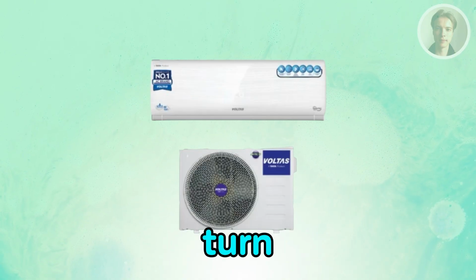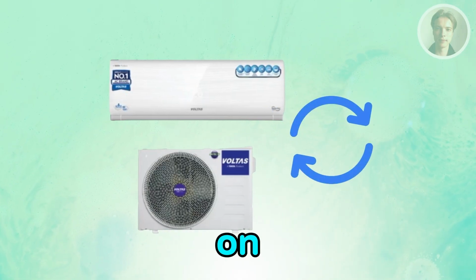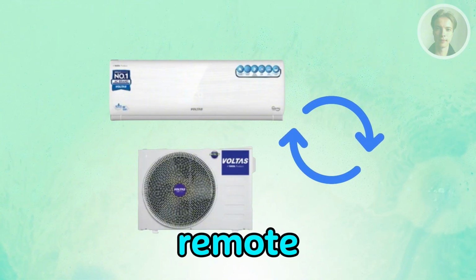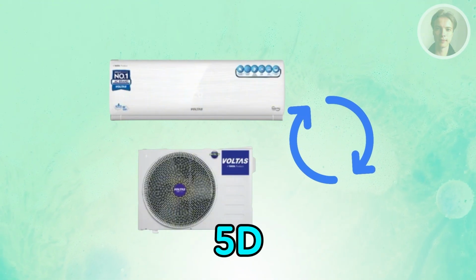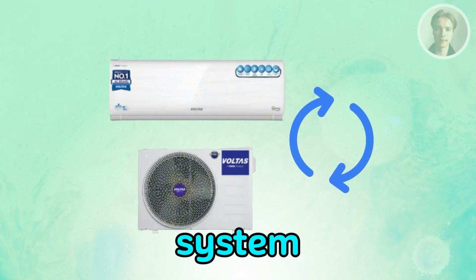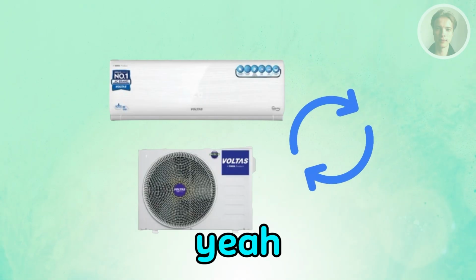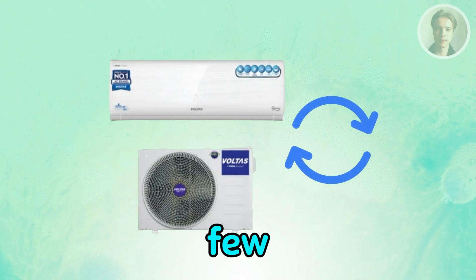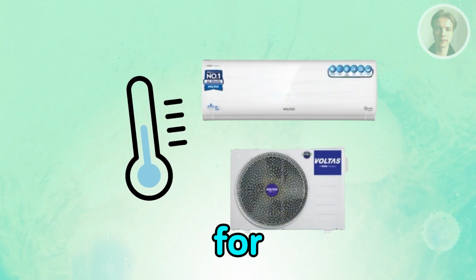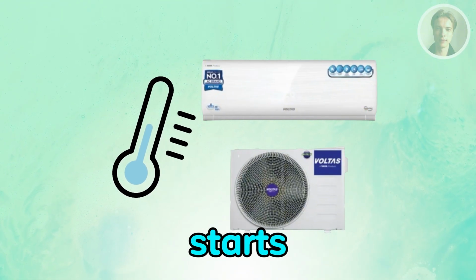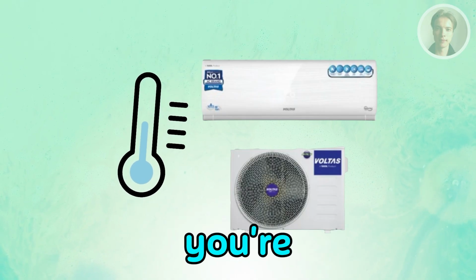Now, you want to turn the wall power back on and start the AC normally with the remote. If the unit runs without showing 5D, the issue was a temporary system fault. So you want to observe the operation for a few minutes if you can. Let the AC run for about 10 to 15 minutes. If cooling starts normally and the error doesn't return, you're pretty much good to go.